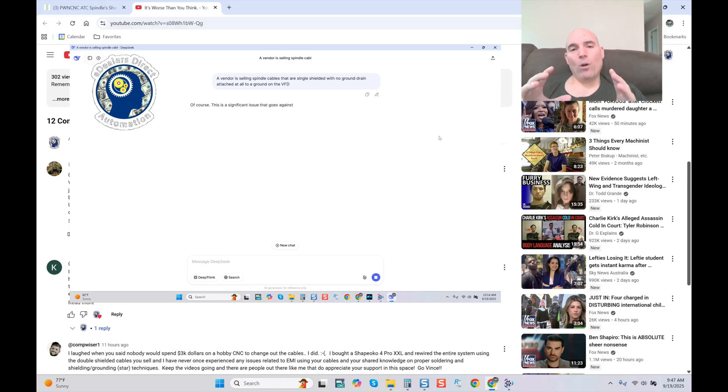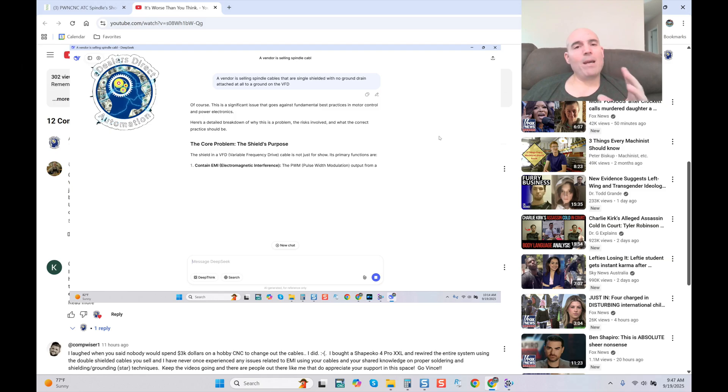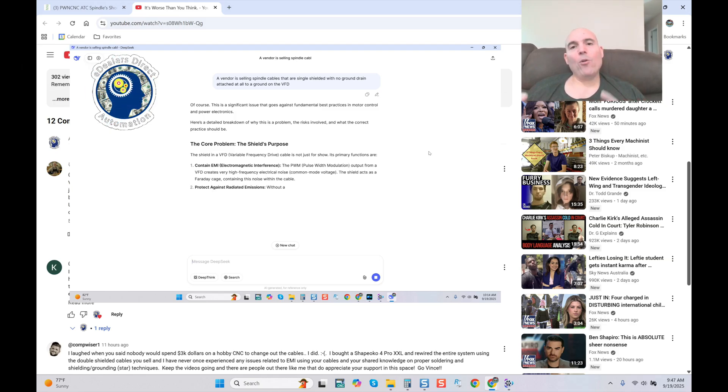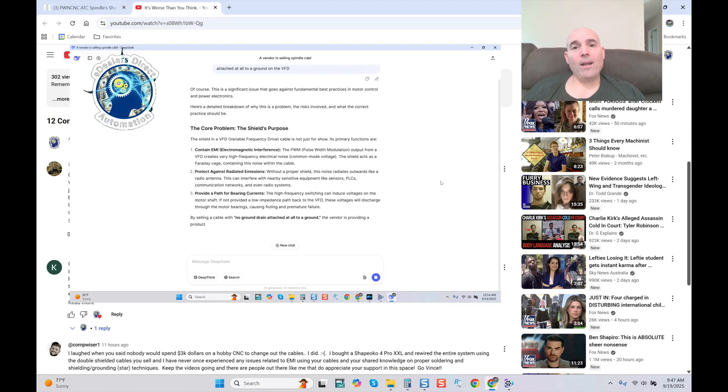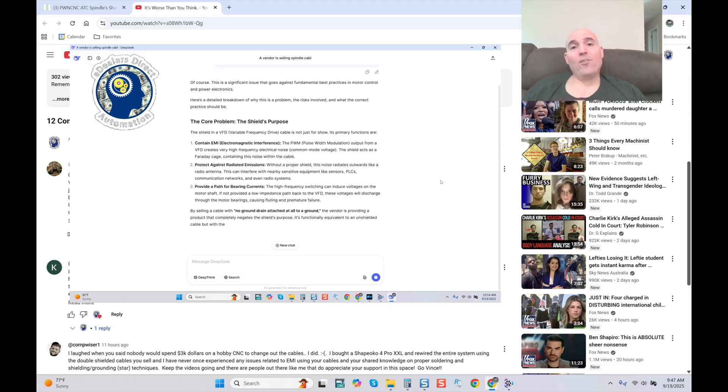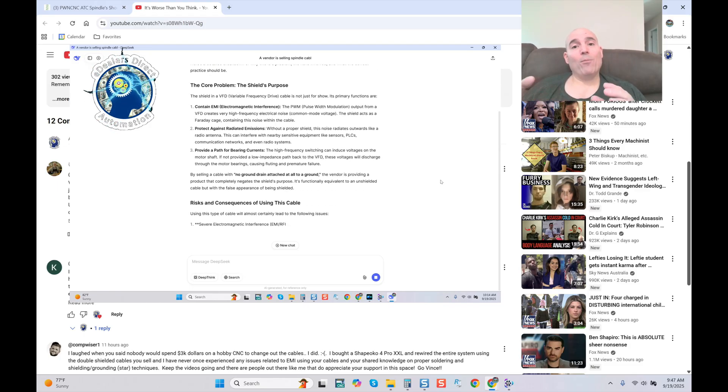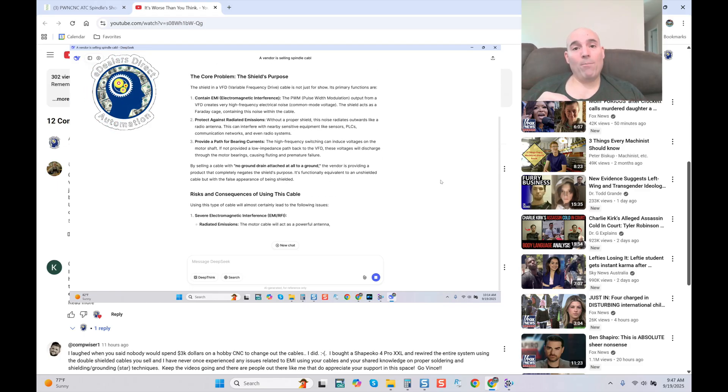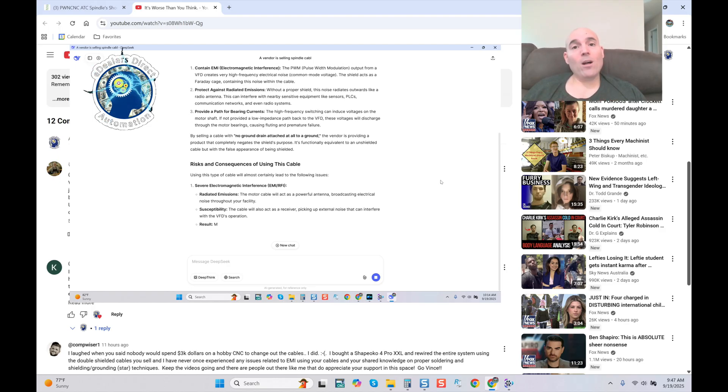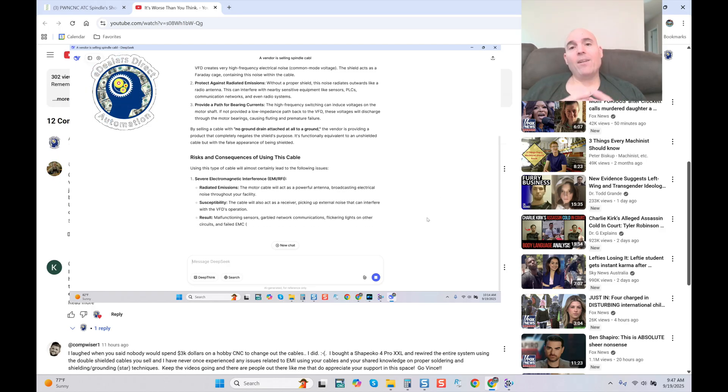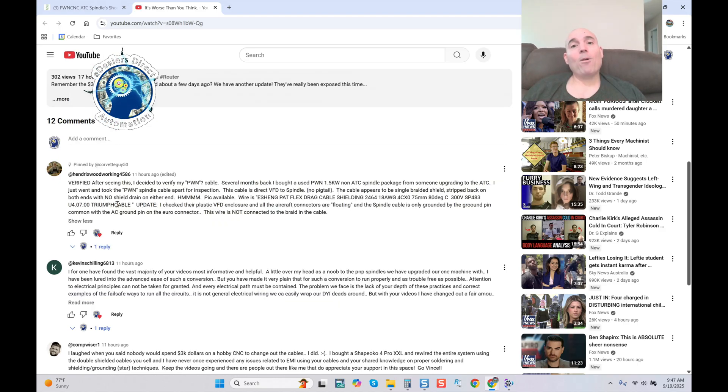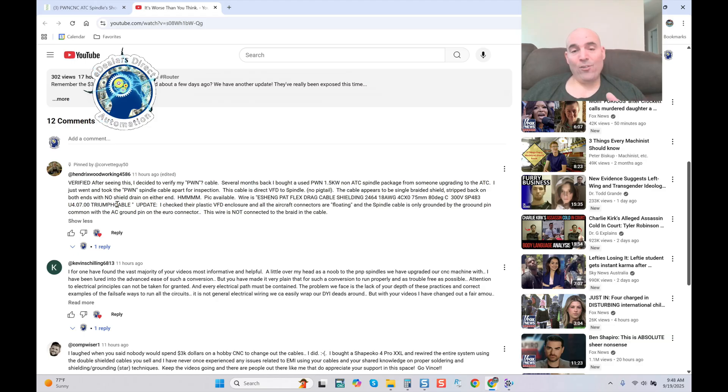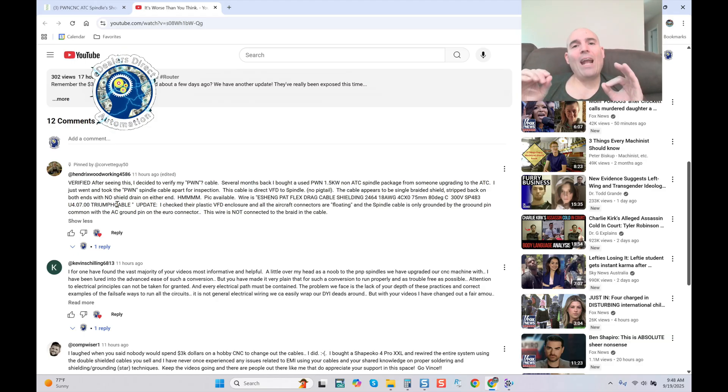No shield drain on either end means that you are dealing with a cable that's just that—a cable. It doesn't matter what shields are internal if there's no way to dissipate EMI. And the only way to do that properly is by attaching a shield drain. In this case, you would hit it to your tin braided copper and you would drain that properly to a ground bus. He's saying on either end of that cable, no shield drain is present, essentially leaving you with just a cable and it does not allow for mitigation of EMI.